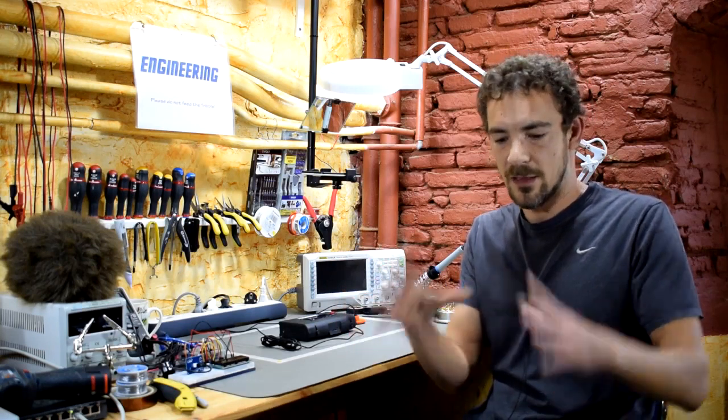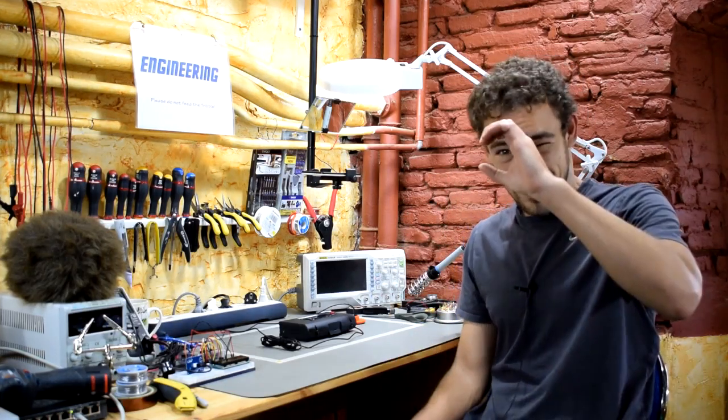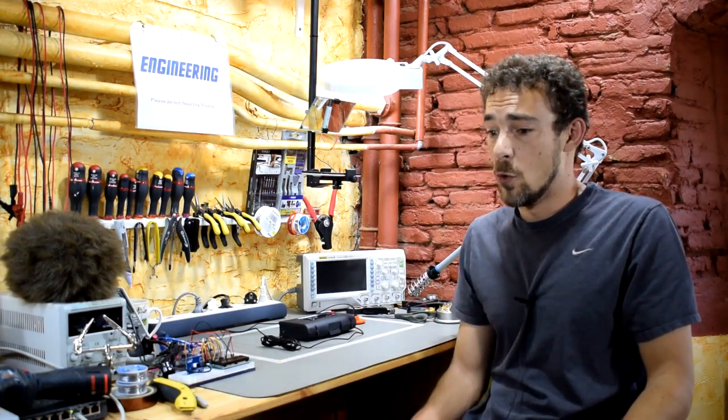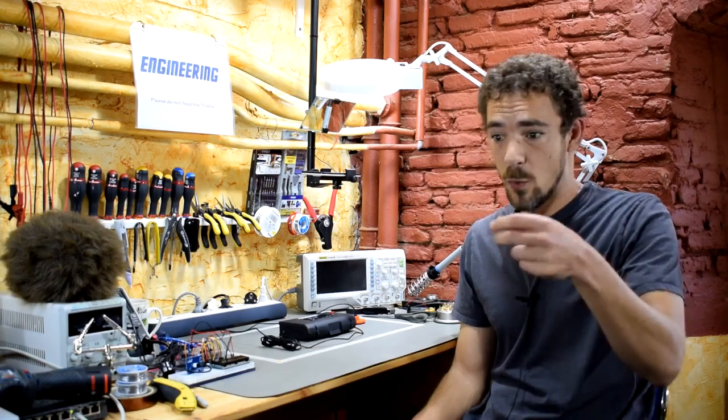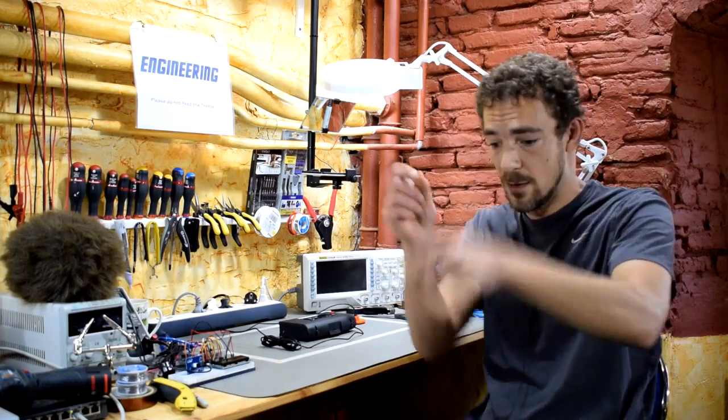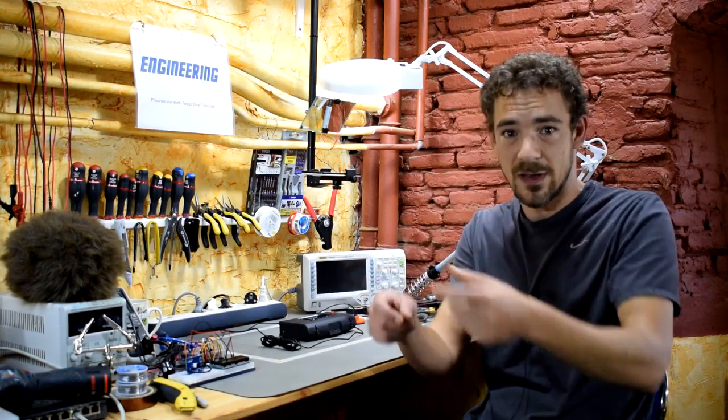Naturally to have a boiler you have to have a fuel tank. The fuel tank I have here is a steel fuel tank. Modern tanks are usually translucent plastic with a large fill cap so you can see the level of the fuel. This one is 30-40 years old, welded steel, and the fill cap is about this big. There are no other entrances to the tank on the top and no fuel gauge. Basically the only way to measure the fuel is to get a weight on a string and put it down the tank, and that's not exactly great.